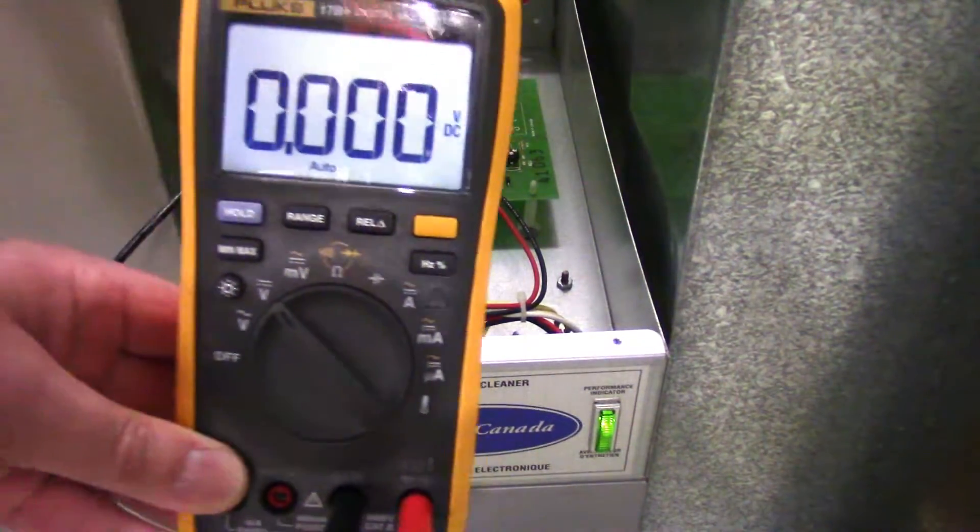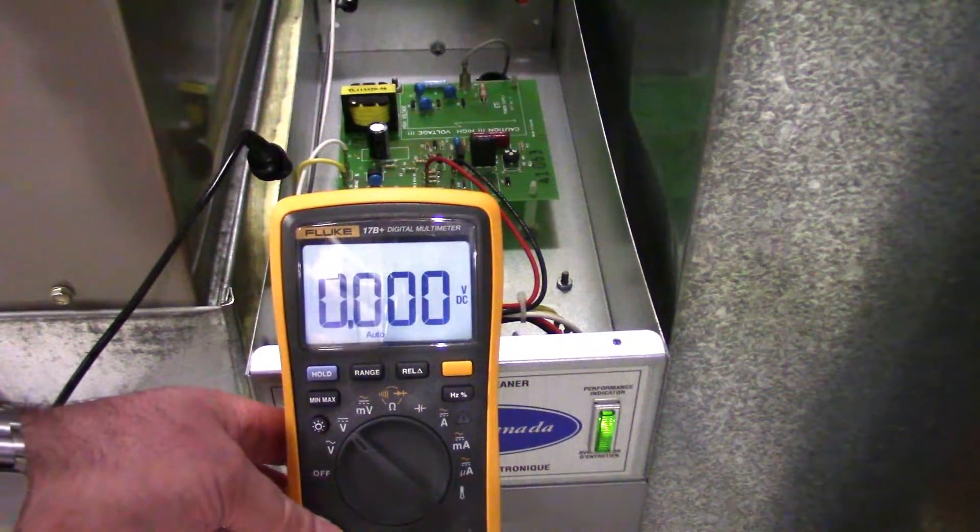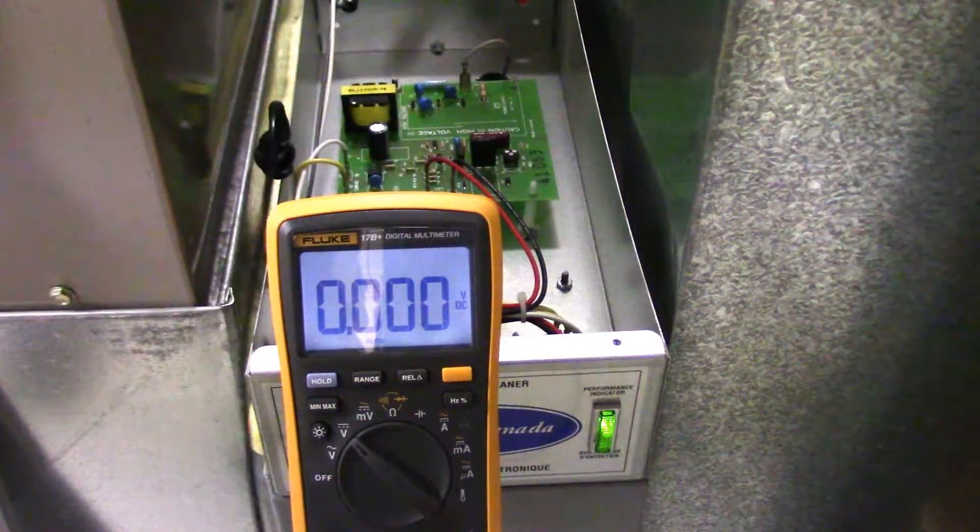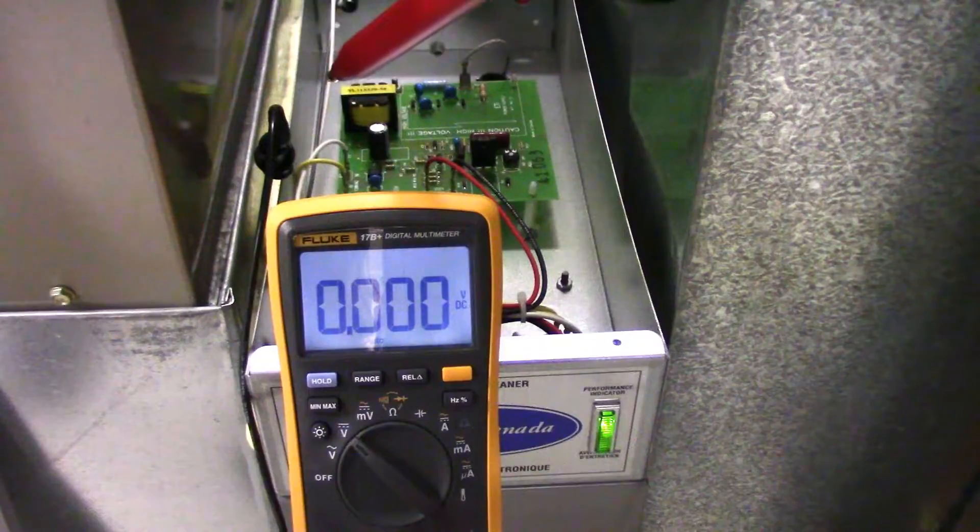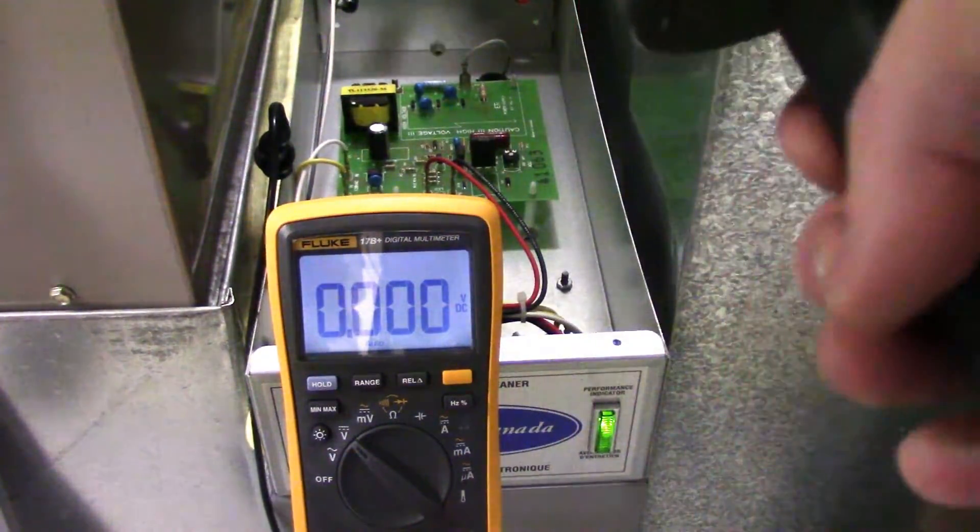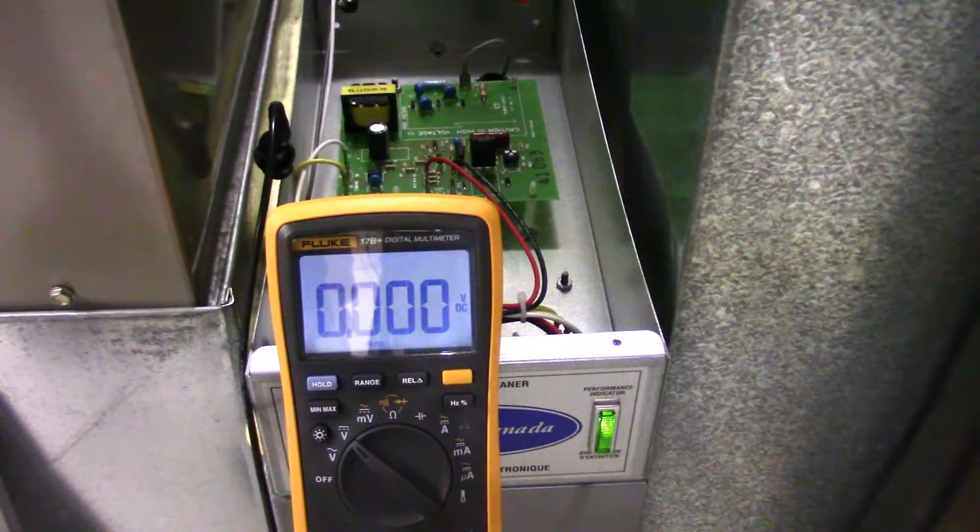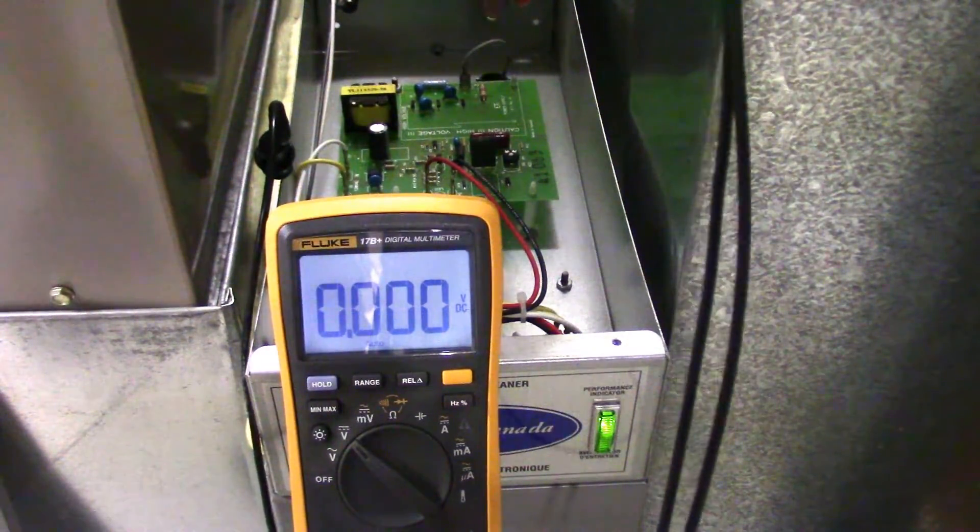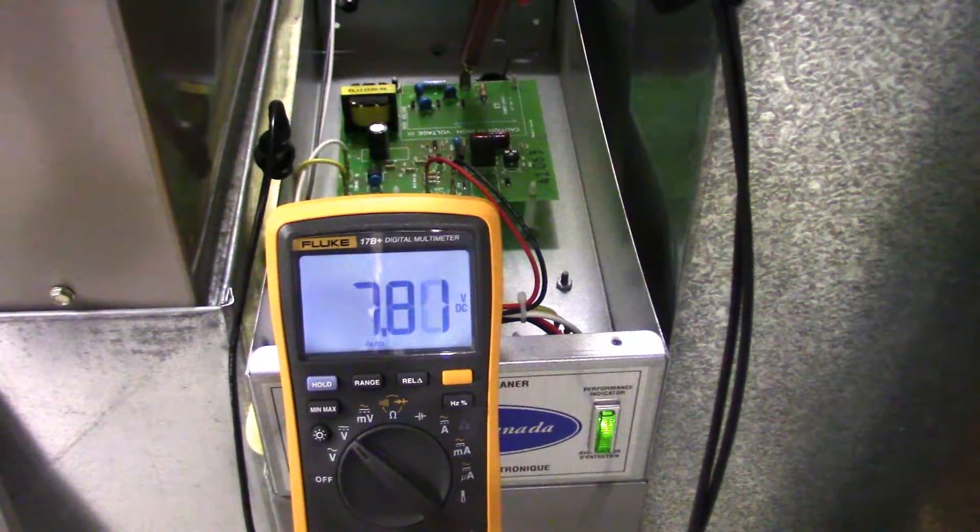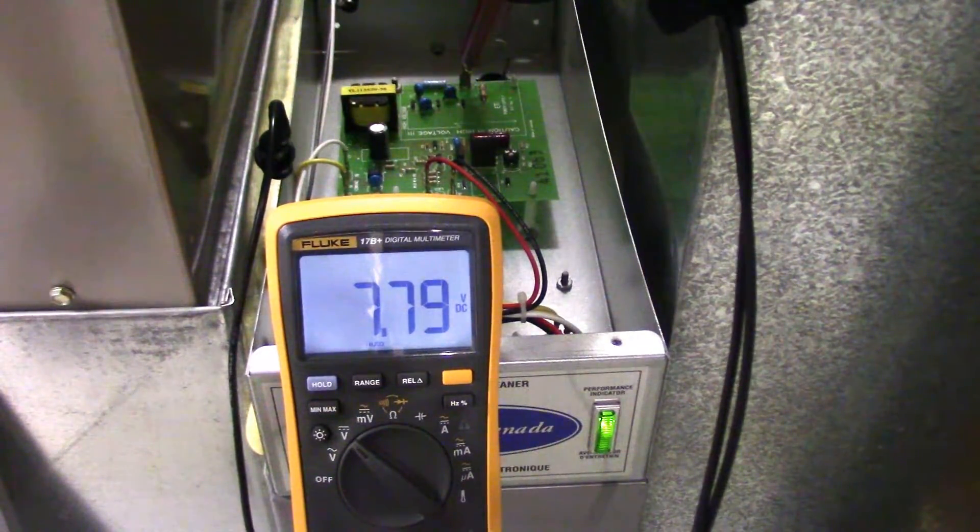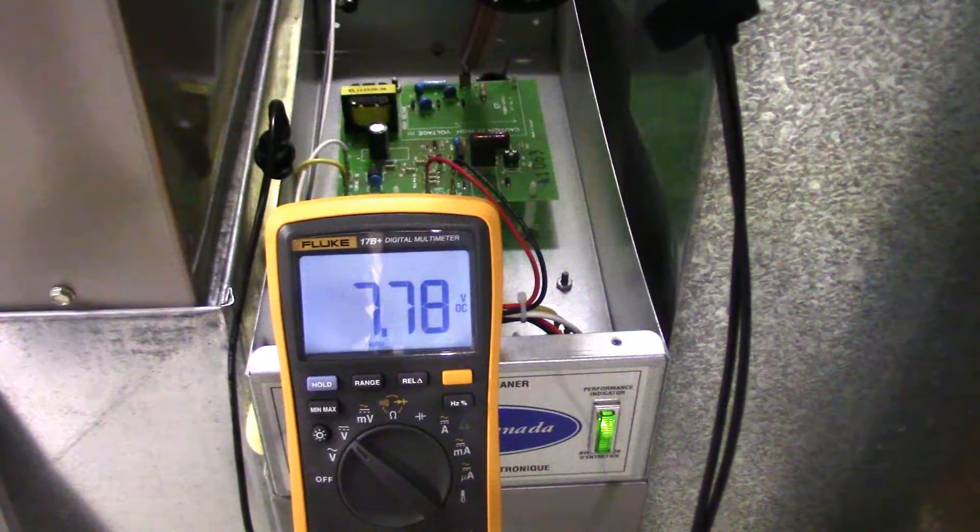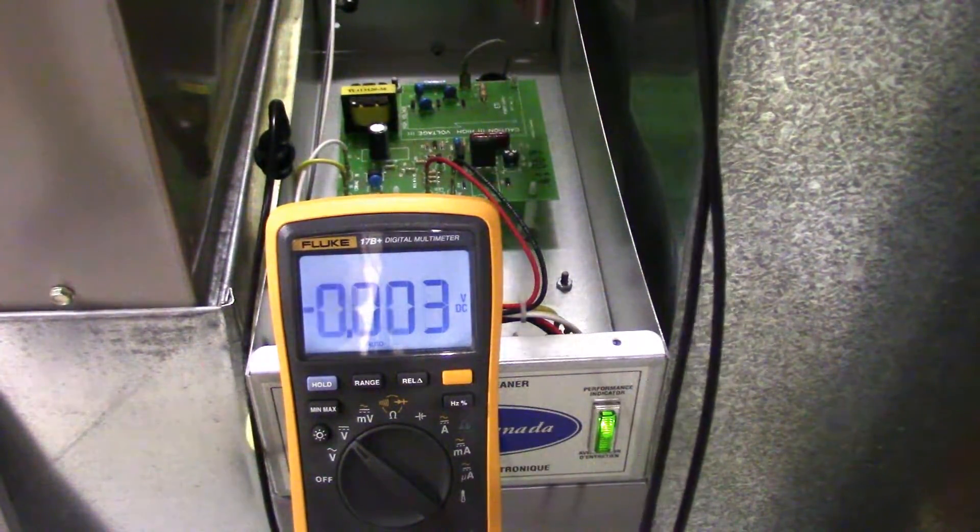Let's do a little HVAC diagnostic work on this electronic air cleaner. I can't find any specs on this thing to figure out what the output voltage is. I heard it can be pretty high though. We've got our grounding clamp on the case of the cleaner, so we're grounded out. Holding our probe with one paw. Got the other paw in the pocket so we don't melt out our brain cells hopefully. And we will touch the output. Oh it's sizzling. What do we got here? 7,790 volts. And that's some serious electron potential there. I'd rather check it with the probe in my tongue.